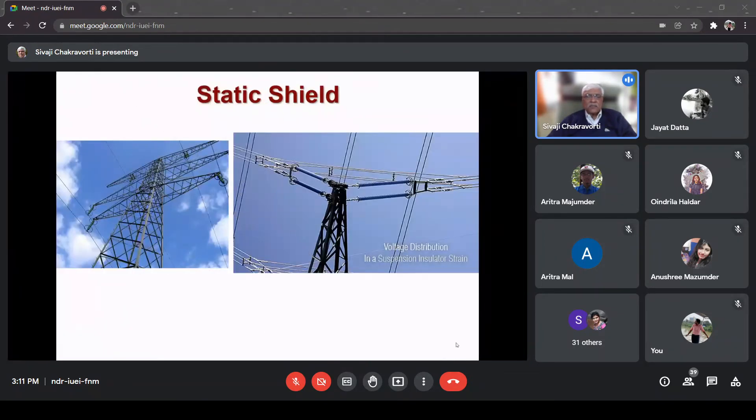Another diagram I want to show you is where you require insulators, not bushings. This is where you can see the transmission line. Here the conductor is not passing through any earthed body but it has to be supported, so from the tower we use insulators for supporting the conductors. Interestingly, on the left-hand side you can see the static shields at both ends of the insulator string - these toroidal structures also help in improving the potential distribution.